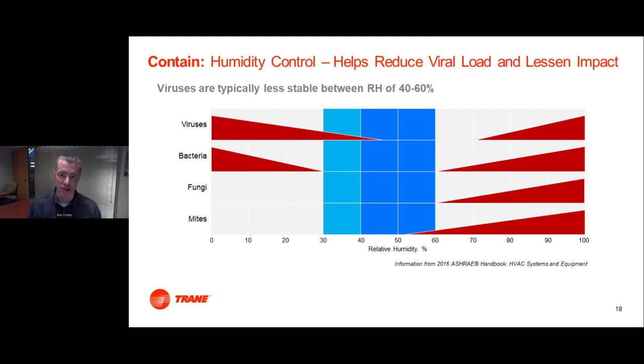The last thing you want to do in a building is get your relative humidity up to 80%, because then you start having mold, fungus issues, some types of bacteria, and even some other types of viruses, not SARS-CoV-2, but other types of viruses actually grow at that higher humidity level. So 40 to 60% is really that sweet spot for humidity in order to reduce risk.